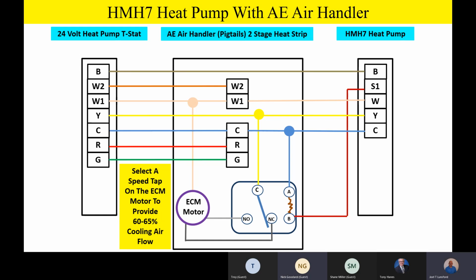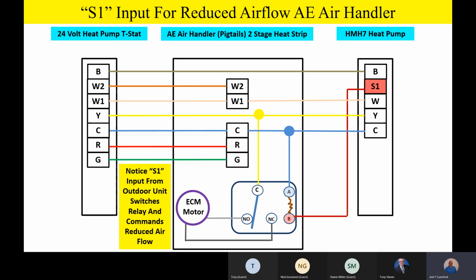Joel, normally closed, what was the airflow? 100%. Good question. On the normally closed contact, we're going to select a speed tap on that motor to provide 100% cooling airflow. So as you can see right now, if I were to energize the thermostat, that normally closed contact, I would automatically get 100% airflow with that relay just sitting there. Good question. All right, at this time, let's go ahead and do that animation.